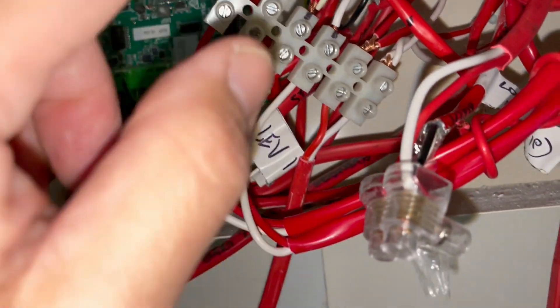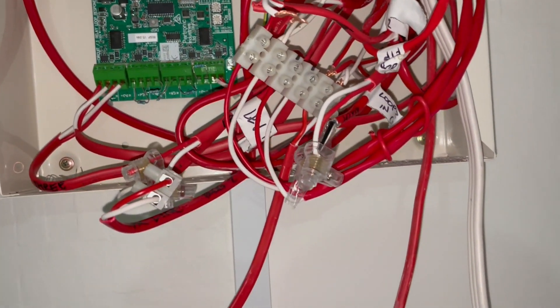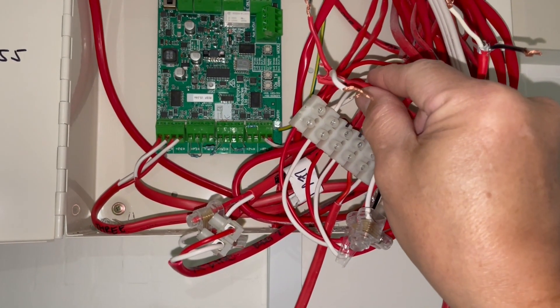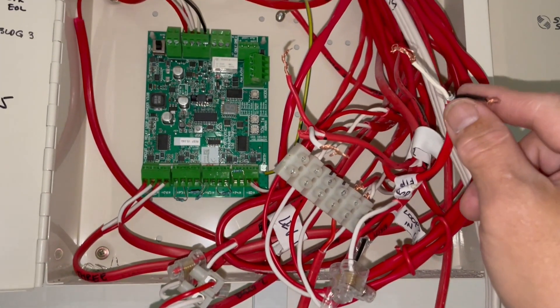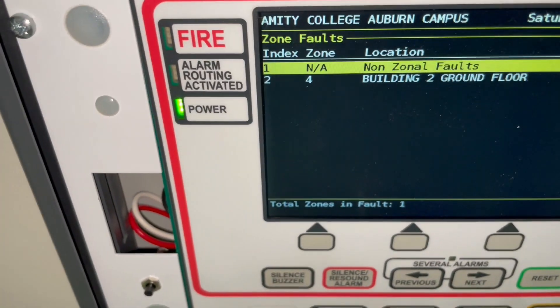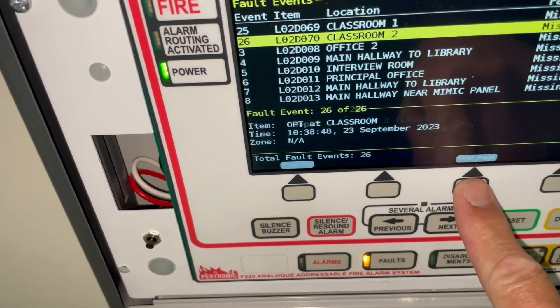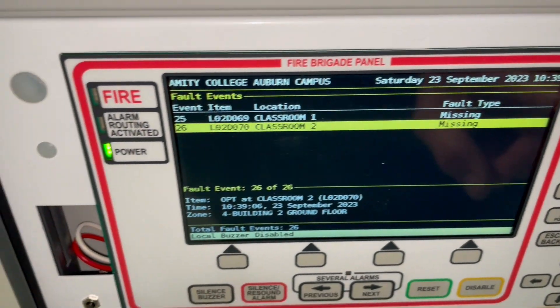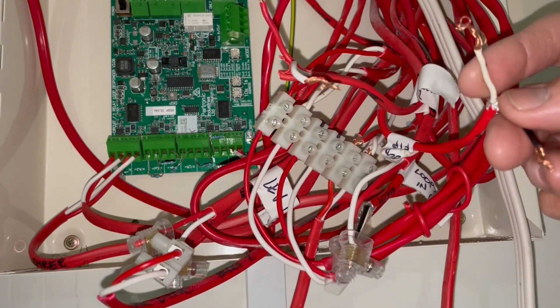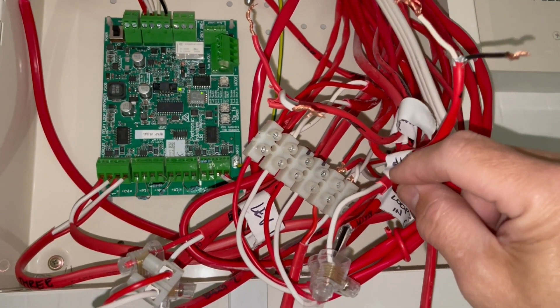So this is the two loops together. What we're going to do is sort out one by one if the fault is coming from this box to the fire panel or from this box to the field and then back to this box. We're going to isolate first the loop coming from the fire panel, both loop in and loop out. What I have done is: this is the loop out going back to the fire panel, and this is the start — or rather the end — of the loop in the building. After connecting the loop out, the earth fault is gone. We have a few detectors on fault right now, but there is no earth fault. So that means it's coming from this end. I'm going to connect loop out to loop in and confirm that loop in and loop out from the fire panel is not the source of the earth fault.